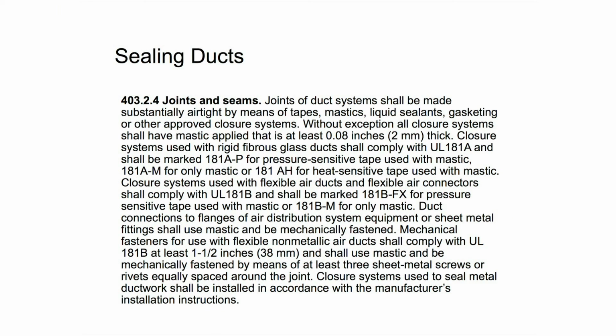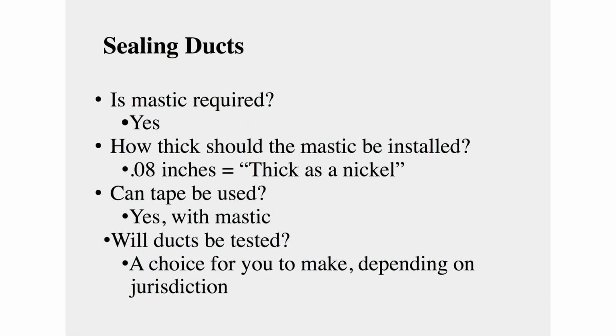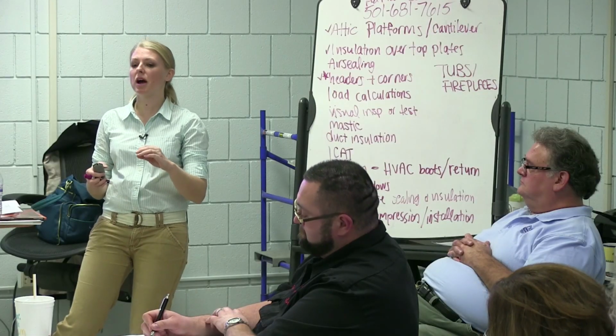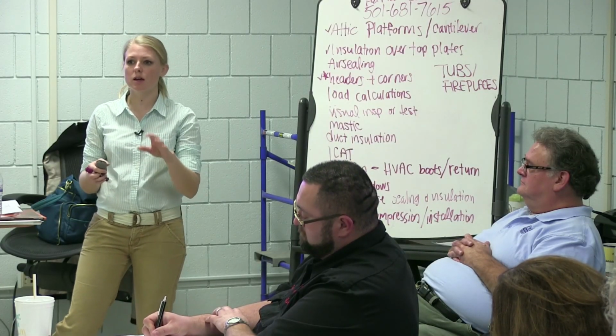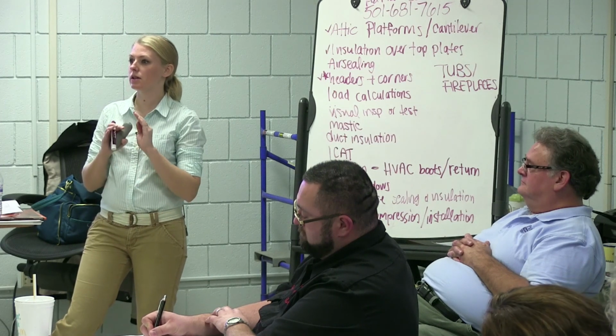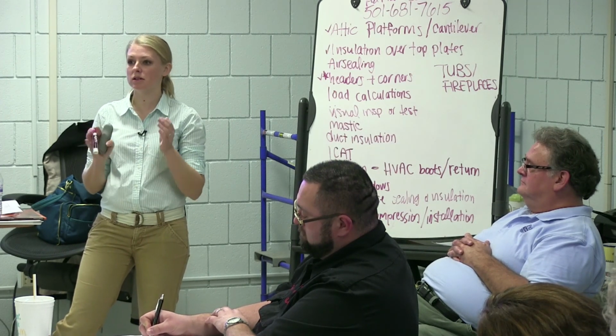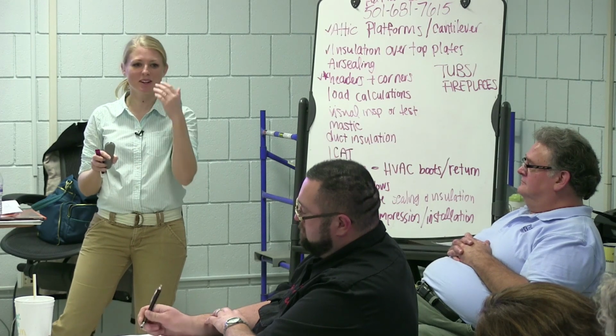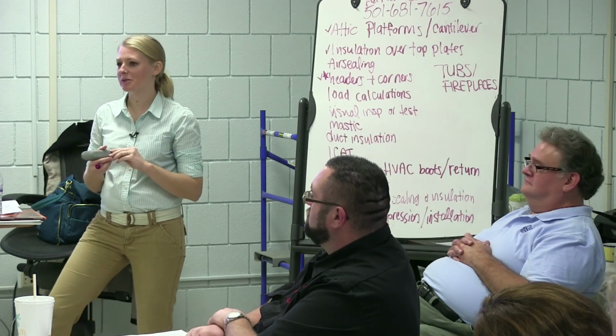About sealing ducts, joints and seams. I am not going to read all of this, but I did read through all of it, and here's what I got out of it. Is mastic required? Yes, mastic is required on all joints and seams. Every single joint and seam of the duct system. Now notice that we're talking about ducts. We are not talking about the air handler unit. The air handler unit is not considered part of the duct system and does not fall under this. You don't need to mastic any air handler panels or anything like that.